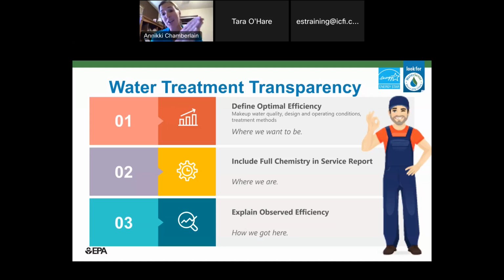So let's say they say, you know what, you buy my product and my service, I'll get you running at 4. That's going to be efficient, save you water, save you costs, and the tower is going to run great. Well, if they don't include this information, we don't know what they're running at. Plus, if they say you could be running at 4, and we see over time we're running at 2, we say, wait a second, what's going on here? Let's reevaluate. So they need to explain to us what the observed efficiency is. Oh, we were at 2 cycles this month because we had a mechanical failure, the water quality changed, something.